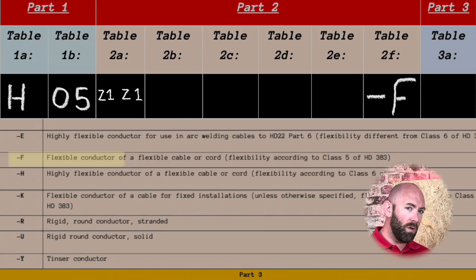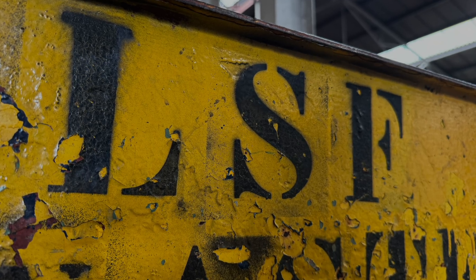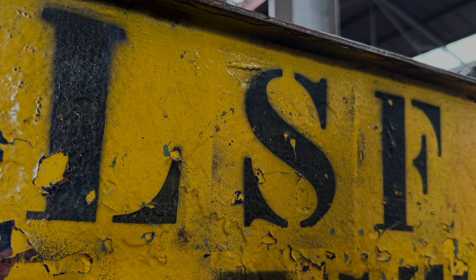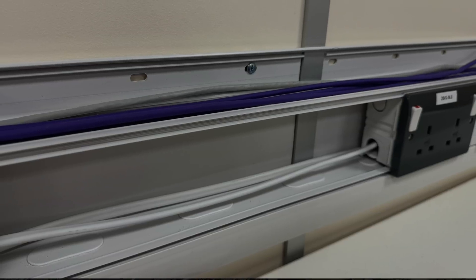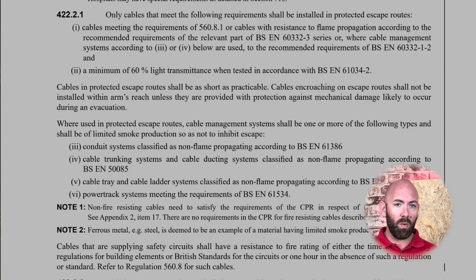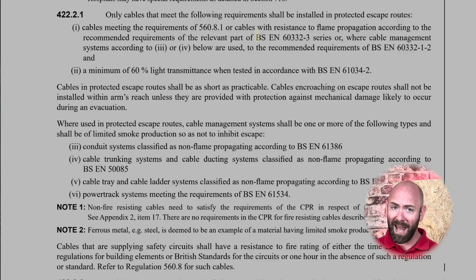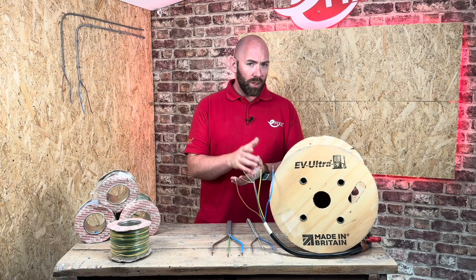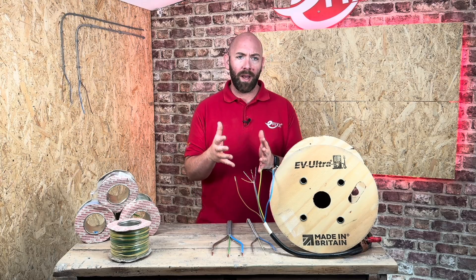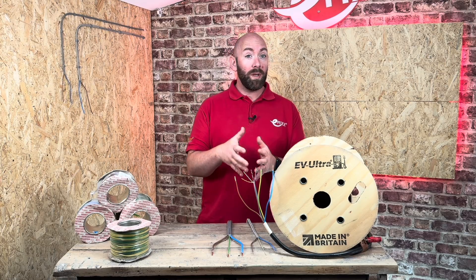The F is that it's flexible. You may know it as LSF cable, meaning low smoke and fumes, and electricians are installing this type of cable in more locations due to how the cable reacts when exposed to fire. Although there is no direct reference in BS 7671 to what cable to use, Regulation 422.2.1 does state that cables shall not encroach on escape routes unless they meet the requirements of BS EN 60332-3 and BS EN 61034-2. These standards require cables to be tested to verify reduced fire propagation and low smoke emissions. So if you are installing bulkhead lighting in a communal area, a cable with the code Z1 will need to be specified for the job.